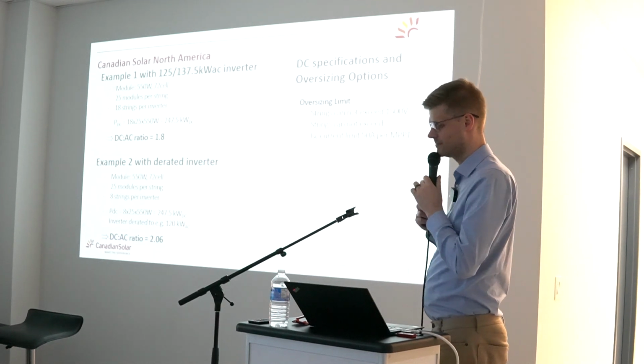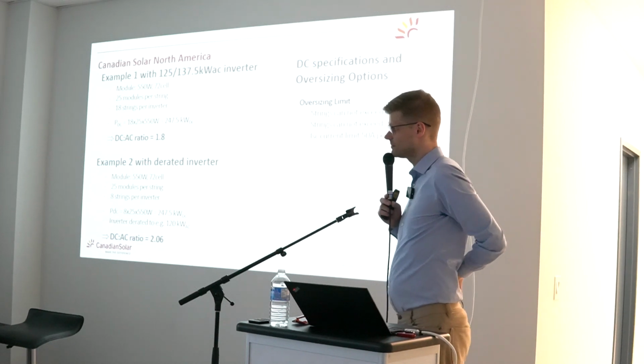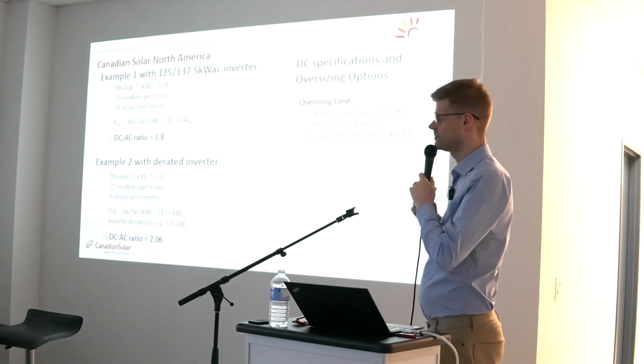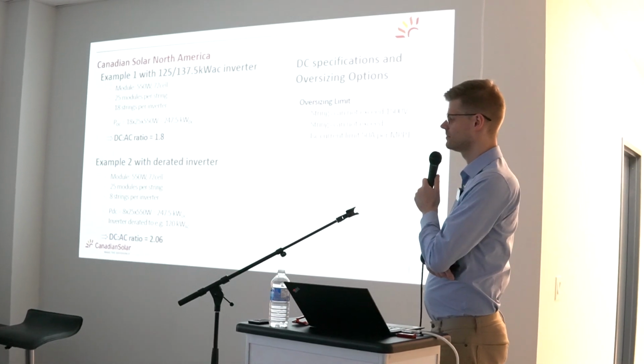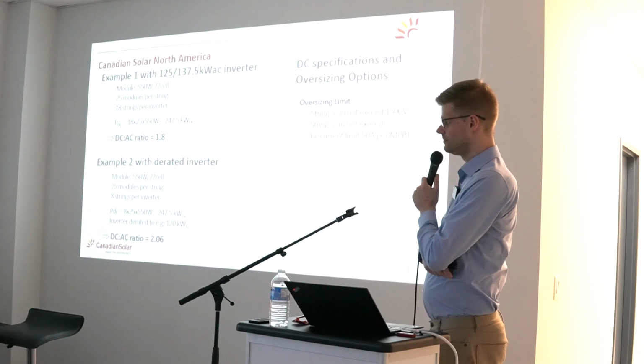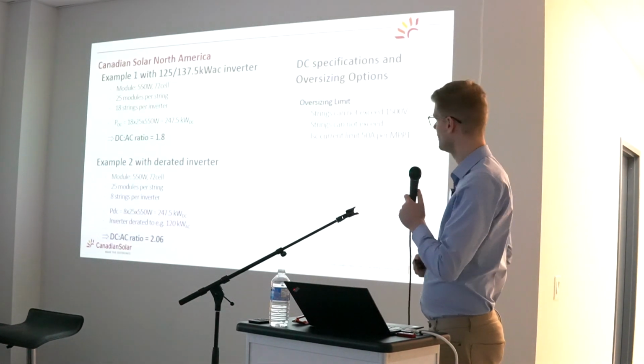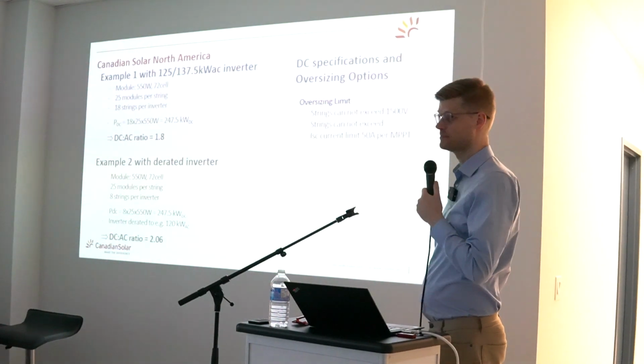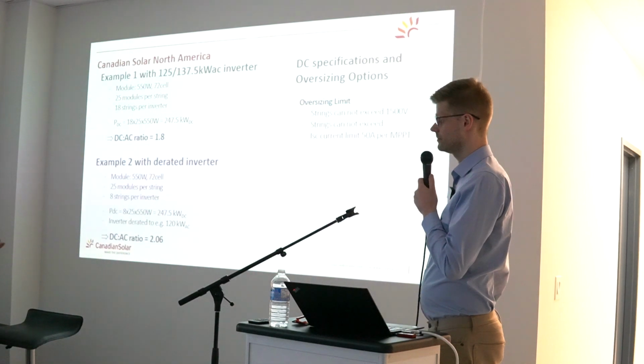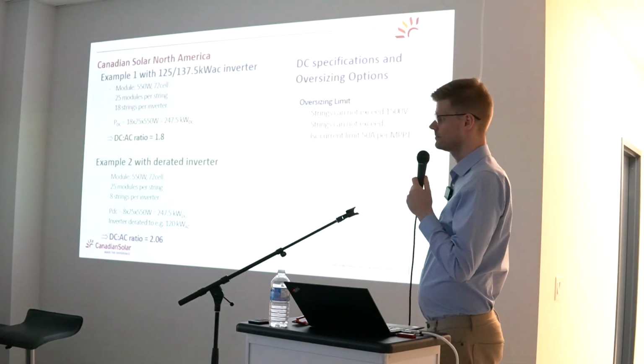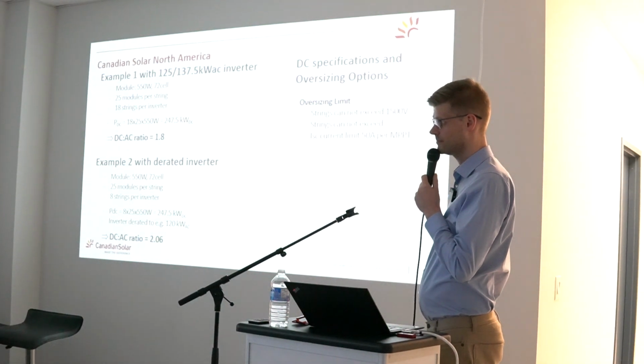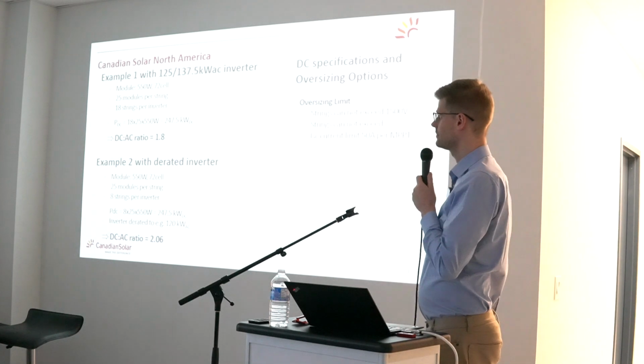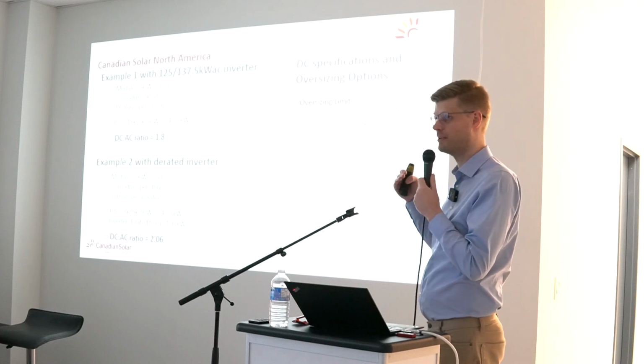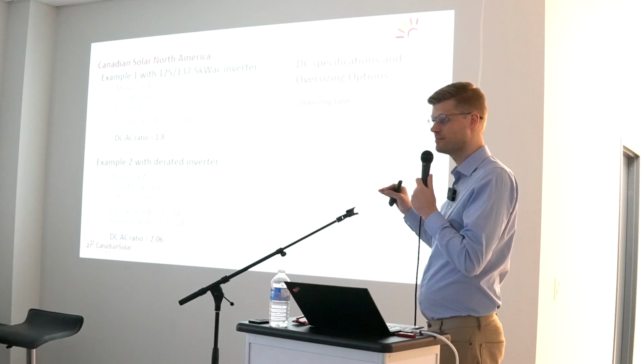So in the past, in Ontario specifically, we had feed-in tariffs, right? Those were typically capped at 500 kilowatts, for example. Out west, Saskatchewan and Manitoba had power purchase agreements that were capped at 2 megawatts AC as well. So how do you optimize that contract capacity? And a lot of times it's with oversizing, right? And yes, in this case, you can oversize more. You buy a few extra inverters, derate them, and then you can add more panels and still stay within the limits of your contract capacity. And this is a case-by-case decision, because every province, every system, every electrical service has different parameters. But you could use those ideas and those tools to really optimize the system specifically for commercial solar.